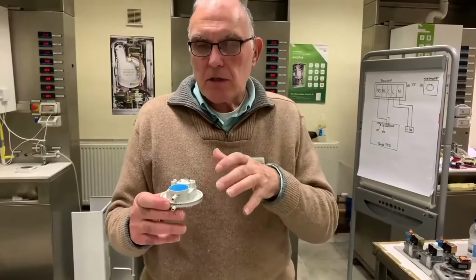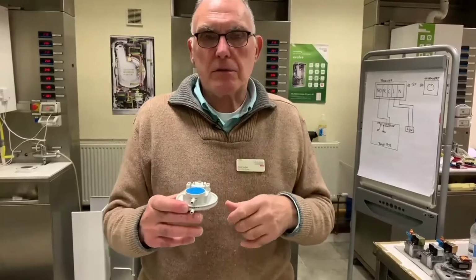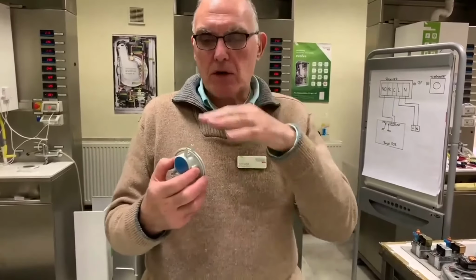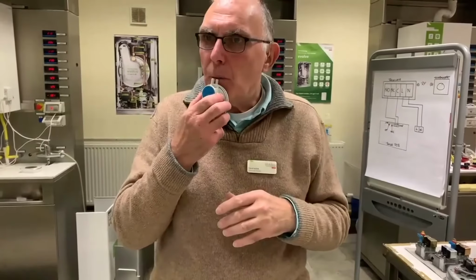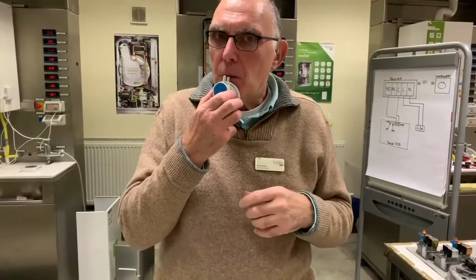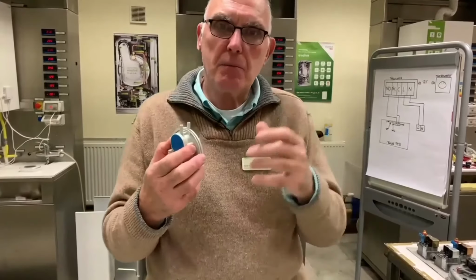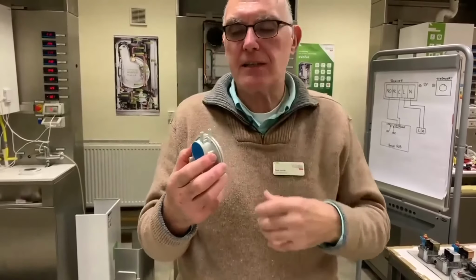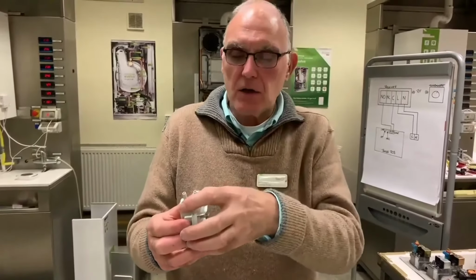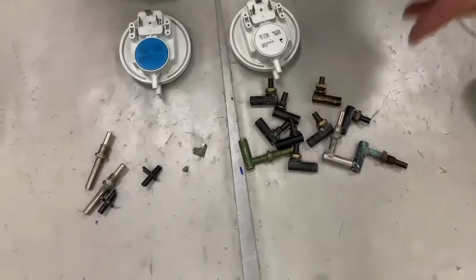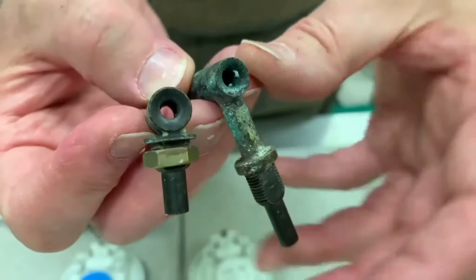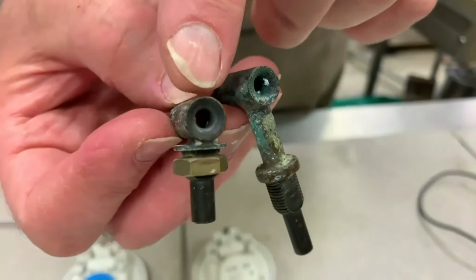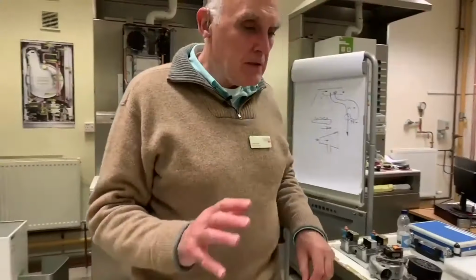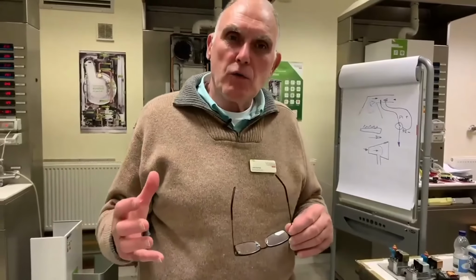These switches can sense 8 pascals. But if you must blow into them, blow across the top. And you could possibly hear that making and breaking, but the whole of your chest isn't going into that diaphragm. If there is any calcium buildup in there, and it could be much smaller than the one you can see on your right. So what I'd like to do now is show you the way our water block works.